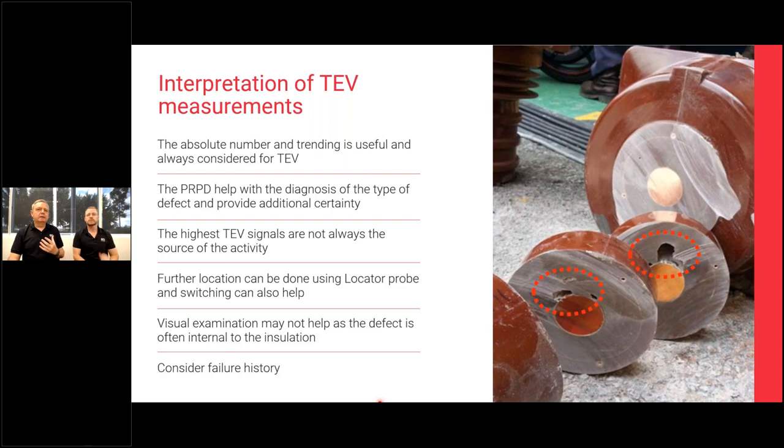To summarize on that, when we're looking at TEV, when you get TEV readings, the absolute number in TEV is actually useful. So it is something that you do consider, unlike ultrasonic. With ultrasonic, like Brad was saying, the level does not necessarily continue rising.